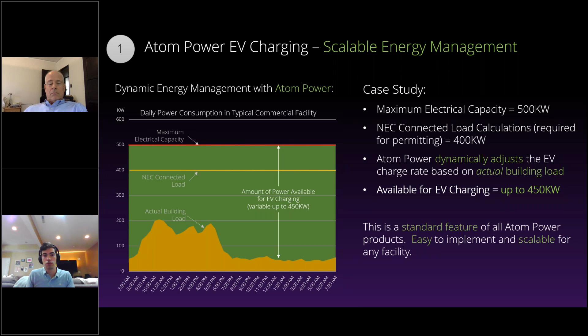I guess you could use, for example, our current 100 amp, kind of like what we're doing here, feeding it. So in a multifamily application, we've seen people use our Gen 3 panel as the main, feeding a main lug only in a residential application, and using this as metering and control and on and off to each one of the residents in the multifamily home, and then having a smaller panel, and you could control certain loads on the home. We do have a single breaker enclosure if you want to use just one of our breakers as well, but we don't have anything available right now that you can just put as the main in a load center.